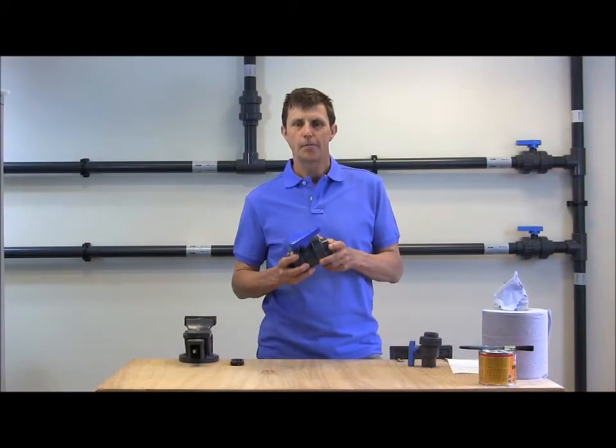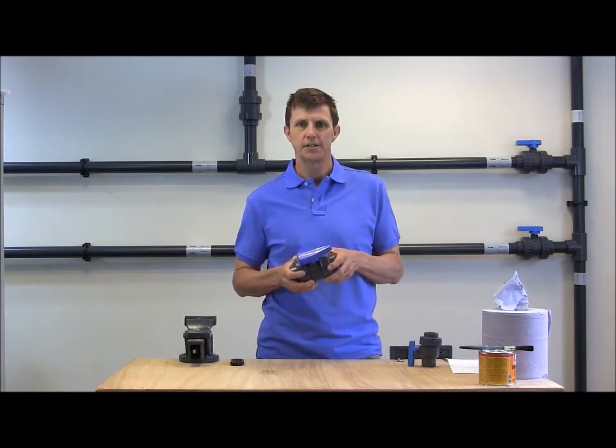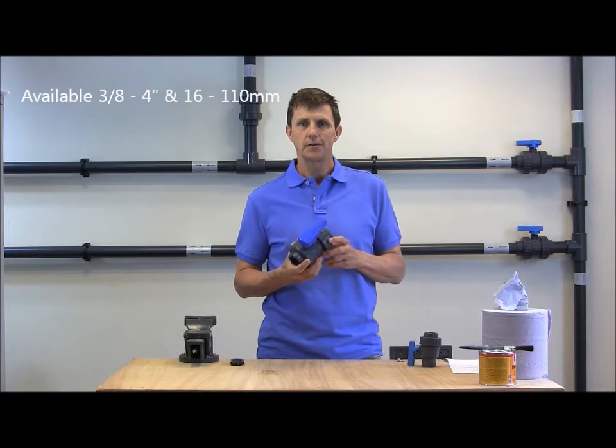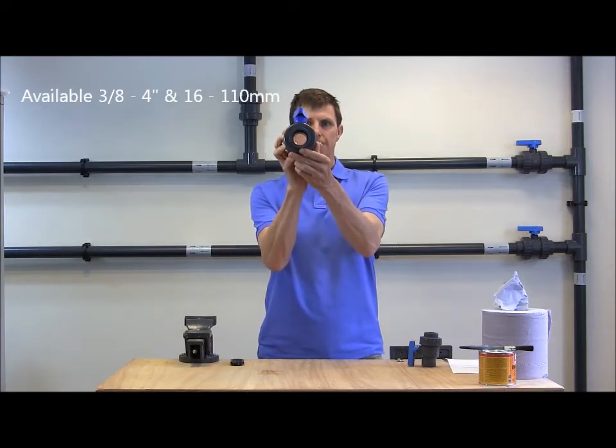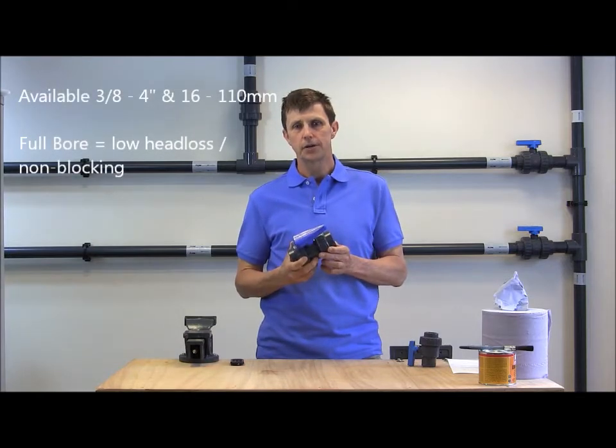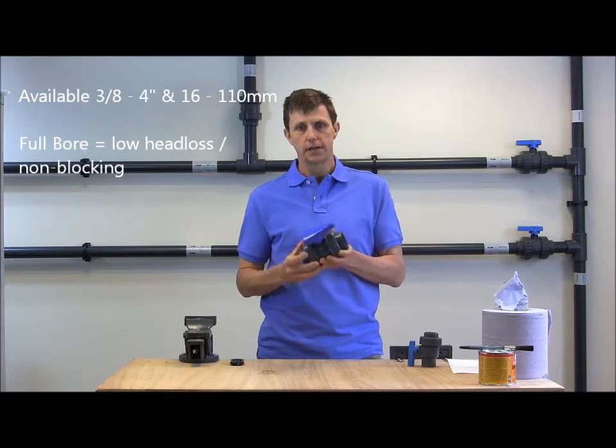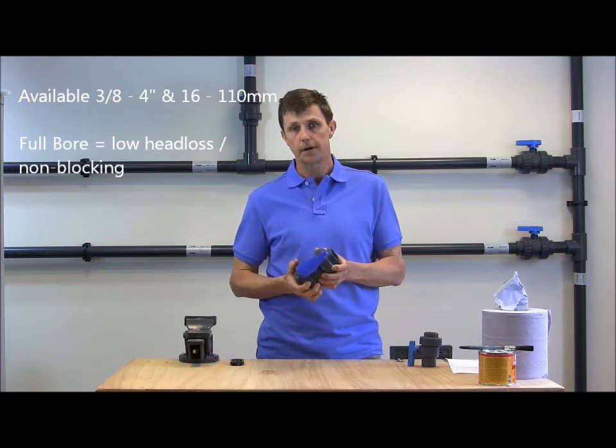Ball valves are probably the most common type of valve you find in pipe systems under 3 inches. That's because they're the lowest cost of any valve and also when they're fully open they run at a full bore, which means there's hardly any head loss but also that there's nowhere for debris or particles to get jammed and block the pipe system up.